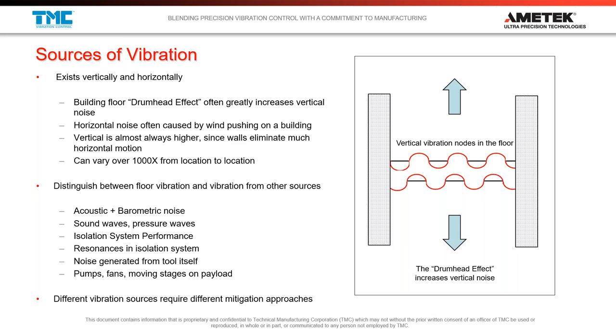Vibration exists both vertically and horizontally. When a building sways in the wind, you might measure that as horizontal left-right or front-back vibration. But it can also exist vertically — tension on the walls as they join the floor creates a drum-head effect, and that torsional mode on the corners of a building can cause the floor to move up and down. Vibration is also like a standing wave — it can vary a thousand times from location to location, with peaks, valleys, and nodes.